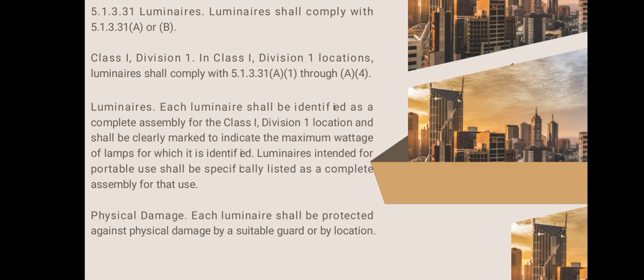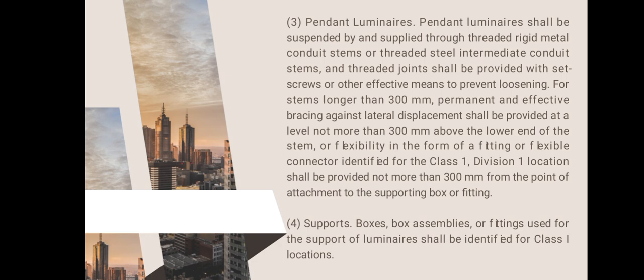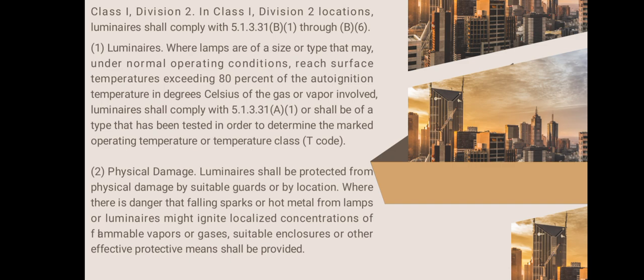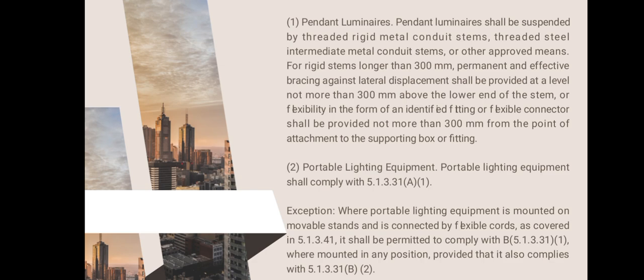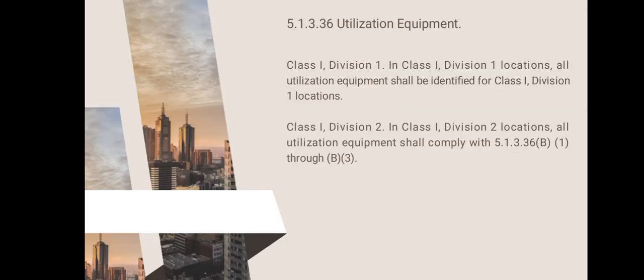So, for luminaires or the lighting fixtures, they must be identified as a complete assembly for Class 1 Division 1 locations and marked with maximum lamp wattage. Protection against physical damage is required. Pendant luminaires must be supported by threaded rigid metal conduit stems or steel intermediate conduit stems with secure joints and bracing. Specific box or fittings types are required for luminaire support. Next, we have the utilization equipment. All utilization equipment must be identified for Class 1 Division 1 locations.